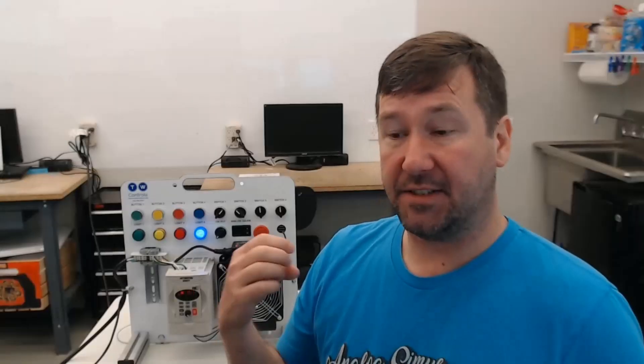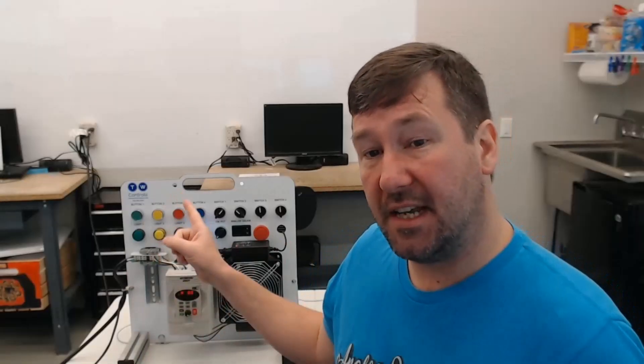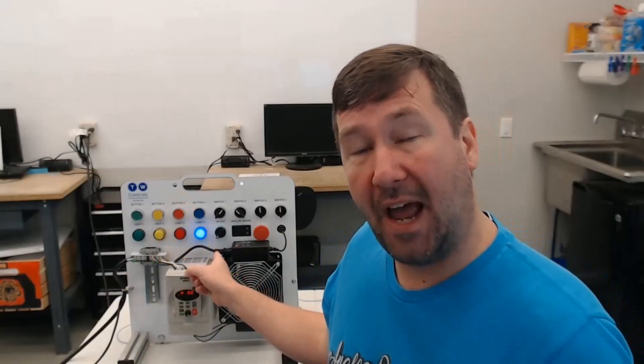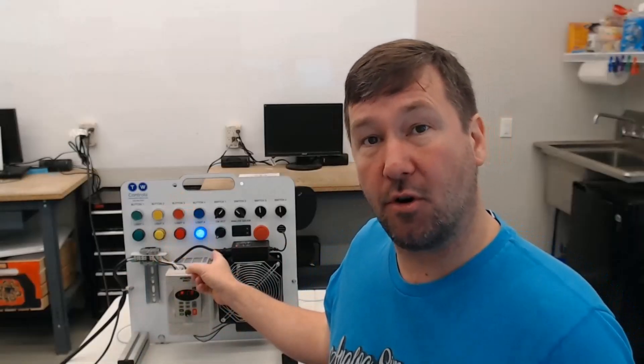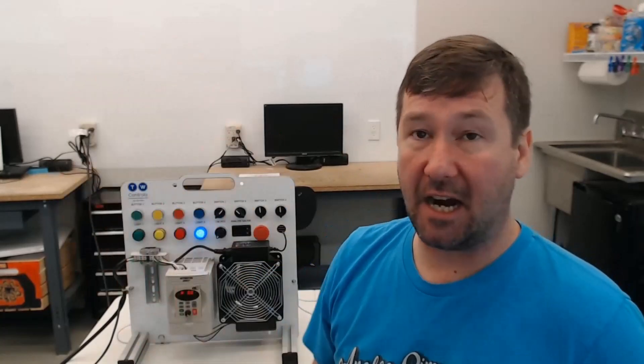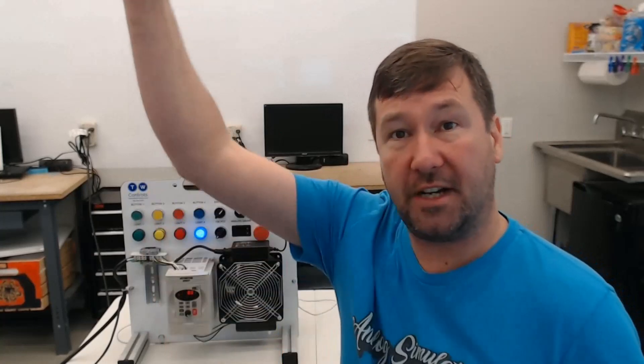So when this PLC power was restored, it actually runs a pre-scan of the entire program. Now guys, you need to understand this one. Because the pre-scan includes all programs, whether they are normally executed or not. We're going to modify this program in a second just to show you. But so it goes through and it scans all of them.